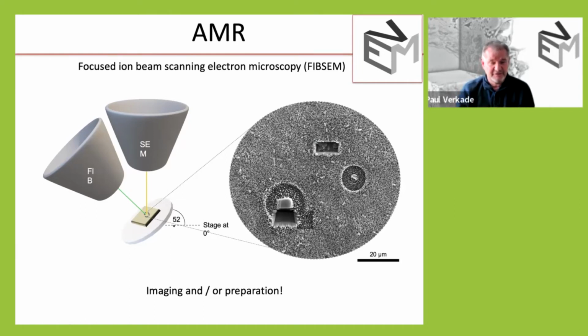You scan that surface, and then you mill away a very tiny layer. And that's the good thing about the FIB-SEM. That has a much shallower depth at which it can mill away. So that can mill away 2 nanometers, 4 nanometers, depending on your needs. And then scan that again. So your overall Z resolution is much higher than you would get for a serial block face SEM.